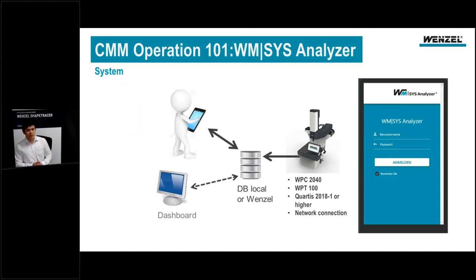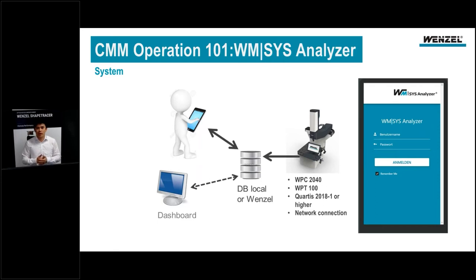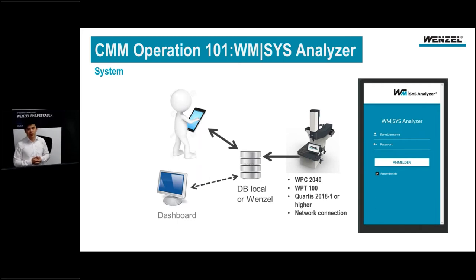Here is the concept of the application. You see a CMM with a controller — the controller collects the data, which is then adapted and processed by a proxy. Clients in the background send this data to a local server or to the Wenzel server, and the user can access it via a web application on a smartphone, tablet, or PC. The requirements are: a CMM with a WPC 2040 controller, a temperature box WPT 100 if you want to display temperature, and measuring software Quartis 2018-1 or a higher version, plus an approved network connection.